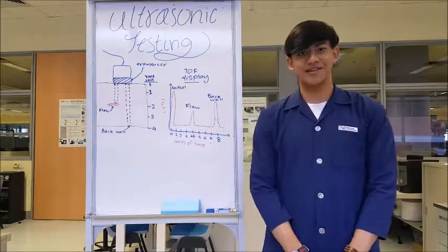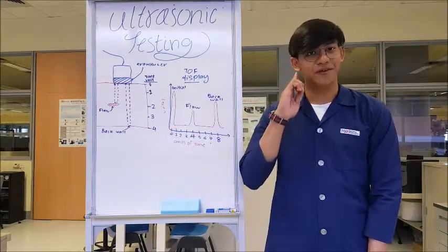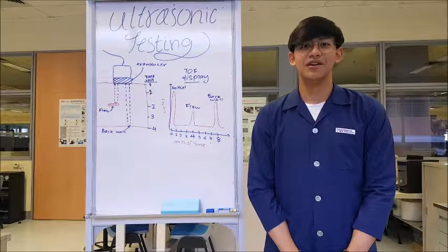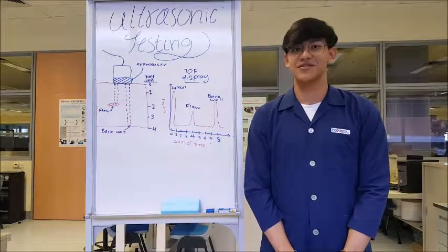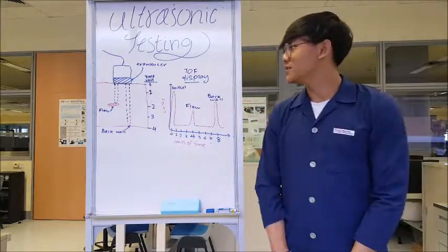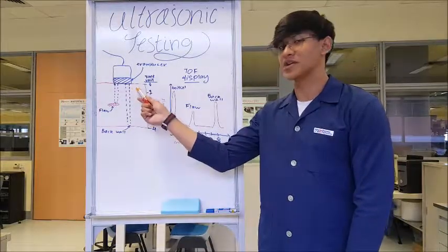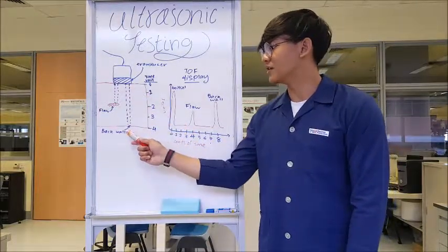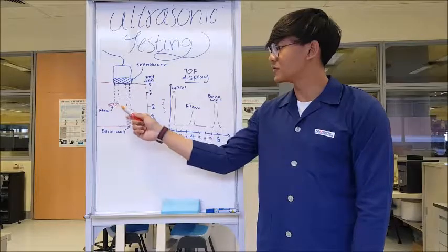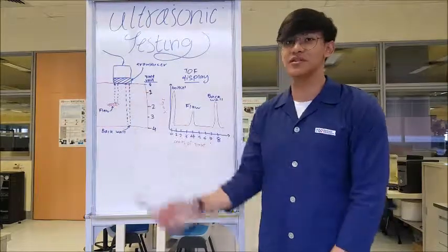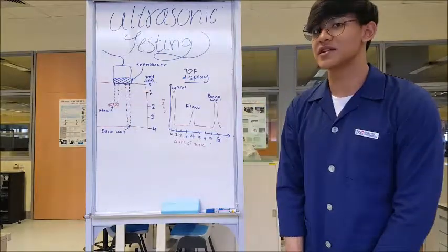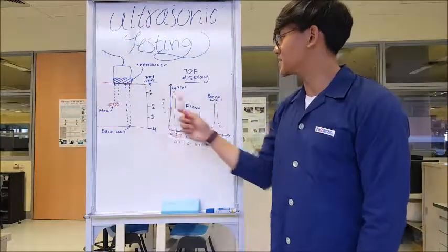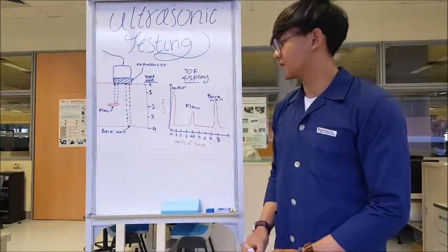Ultrasonic is sound energy above the audible frequency of 20,000 Hz. Due to its high frequency, it has good penetrating power. When this sound energy is introduced and propagates through a material, it could hit a back wall or a flaw, where it will be reflected back up into the transducer. The reflected signal can then be sent to a display where you can see the result.